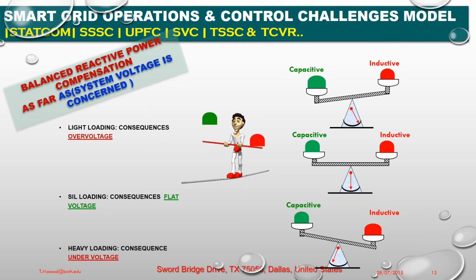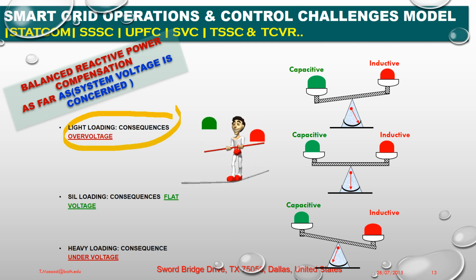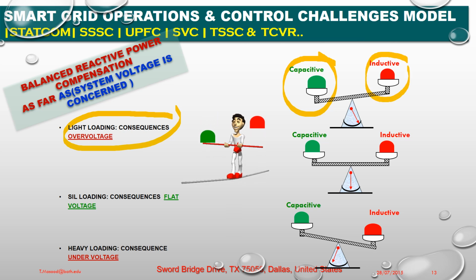In lecture number 2, we discussed the consequences of imbalanced compensation. If it happens, what could be the impact on power system operation? In this lecture, we are going to discuss balanced reactive power compensation as far as system voltage is concerned. First, light loading. What could be the consequences? Over voltage. It is capacitive or more, and inductive is less, so the system is compensated in the capacitor mode of operation.